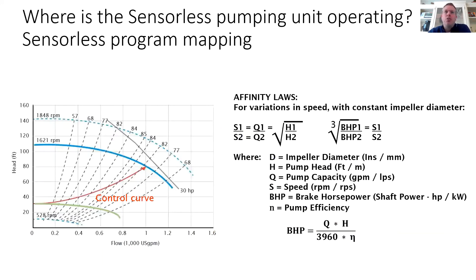So all sensorless control pumps are tested complete with pump motor controls package by recording the flow, head, power, and speed at 10 points along the maximum speed curve and at 90 other points along 9 other speeds all the way down to the pump minimum speed set point. So all this data, these pump coefficients are then uploaded into the controls map for that specific pump so that we know the exact flow and head at any power and speed combination, which is being measured by the controller on site. So this is cutting-edge technology for pump controls, but Armstrong has actually been using this type of data in their selection software for over 25 years.